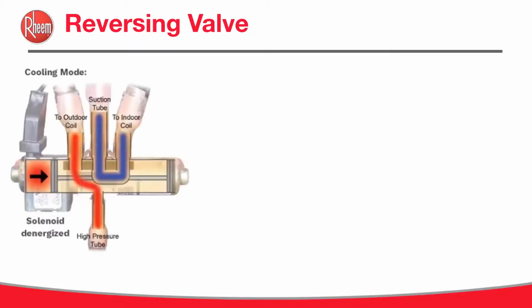So now let's look at reversing valves. Again, this is a component that's not used in an air conditioner. Why do we need a reversing valve? Well, reversing valves are used in heat pumps to redirect the flow of refrigerant for the heating and cooling modes. So as you can see here, this one is in cooling mode when it's de-energized, right? As we said, our systems are de-energized in cooling mode. Why? Well, you can put strip heat on if you need heating in the winter, but if a reversing valve is stuck when you go to move it, there's no way you can put any type of cooling in your house. So that's why we fail to cooling mode.